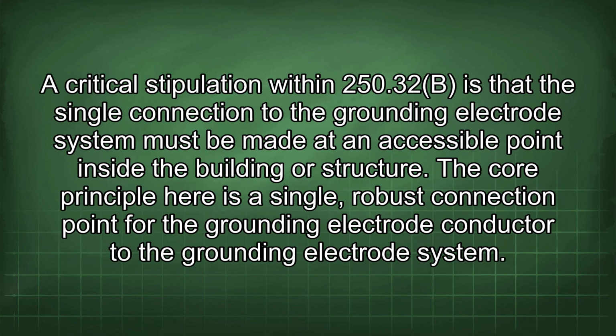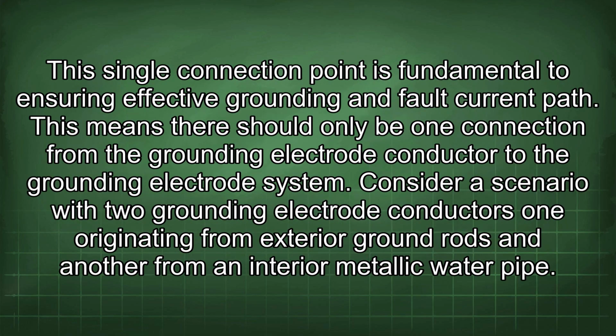A critical stipulation within 250.32(b) is that the single connection to the grounding electrode system must be made at an accessible point inside the building or structure. The core principle here is a single, robust connection point for the grounding electrode conductor to the grounding electrode system. This single connection point is fundamental to ensuring effective grounding and fault current path. This means there should only be one connection from the grounding electrode conductor to the grounding electrode system.